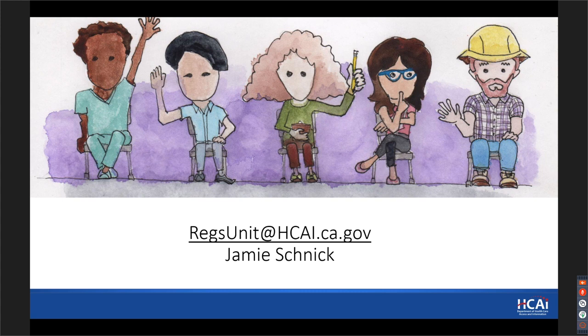Thank you. Next question: can a transformer be installed above the panel it serves within the dedicated panel space? Would it violate code section 110.26(E)? Yeah, that would be a code violation. Short and sweet. Thank you, Jamie.